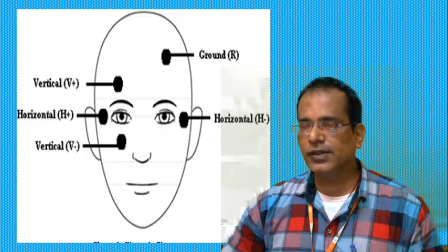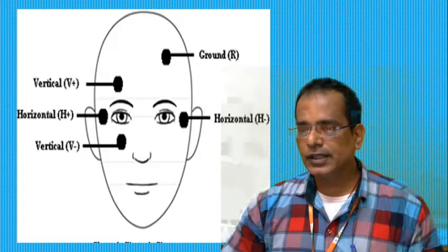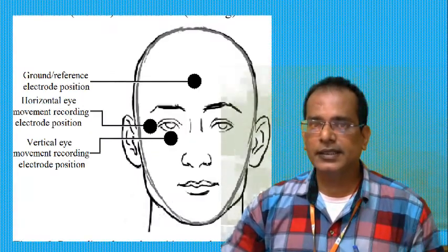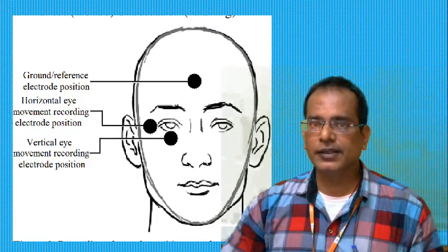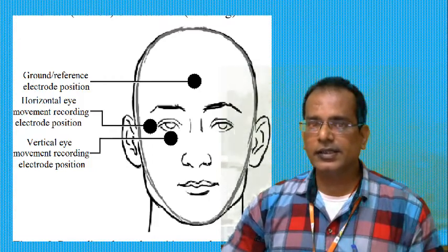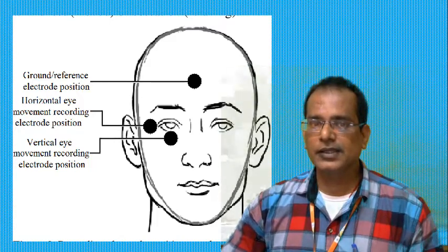The EOG picks up the inherent voltage of the eye during open-eyed wakefulness. Sharp deflections in the EOG tracing may indicate the presence of eye blinks. The forehead electrode serves as the ground reference. The horizontal electrode pair H+/H− records horizontal eye movement, and the vertical electrode pair V+/V− records vertical eye movement.